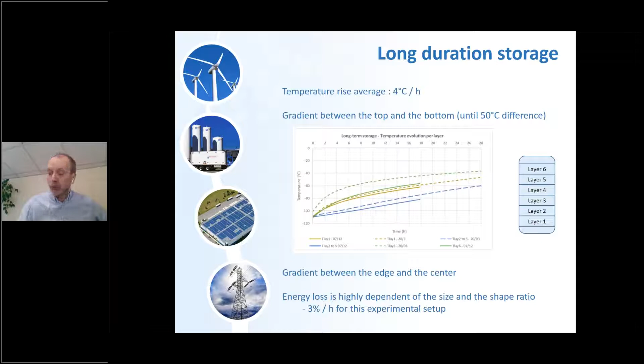These experiments were very interesting for learning about this storage process. What we could also see is relevant to long duration storage. Even though the insulation thickness in this tank was 200 millimeters, the thermal losses were far from negligible. During long duration storage, an average of 4 degrees per hour of temperature loss could be observed. During this storage phase, we could also measure an important temperature gradient between the top and the bottom, and between the center and the edge, because of thermal losses through the wall. So many results were a little different from the simulation, and we could learn a lot from the experiments.